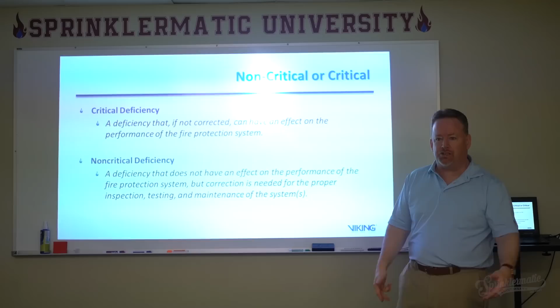That's judgment. The other challenge here with these particular definitions, a little inside baseball for you, is that nowhere else in the standard are these terms used. Nowhere else does it say if paint is on the sprinkler, this is a critical deficiency, period, end of story, as a non-judgment statement. They have some material in the annex that explains, if you've got a little bit here or a little bit there, but what's that again? It's judgment. It's a judgment call, making it almost impossible to apply either of these two terms.